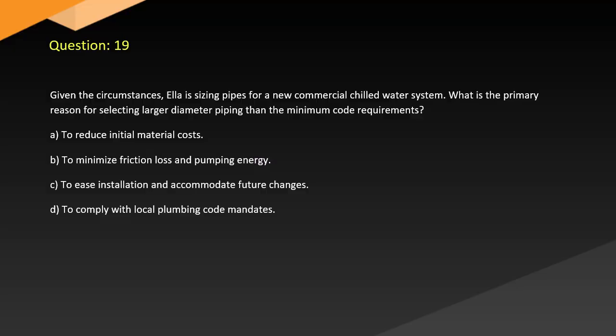Question 19. Given the circumstances, Ella is sizing pipes for a new commercial chilled water system. What is the primary reason for selecting larger diameter piping than the minimum code requirements? A. To reduce initial material costs. B. To minimize friction loss and pumping energy. C. To ease installation and accommodate future changes. D. To comply with local plumbing code mandates.